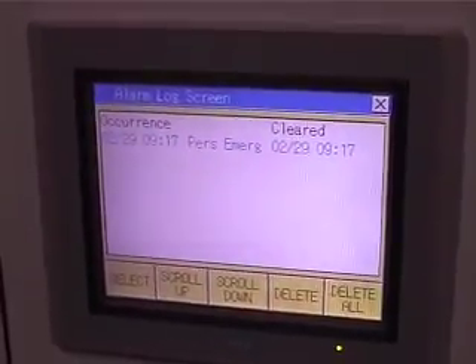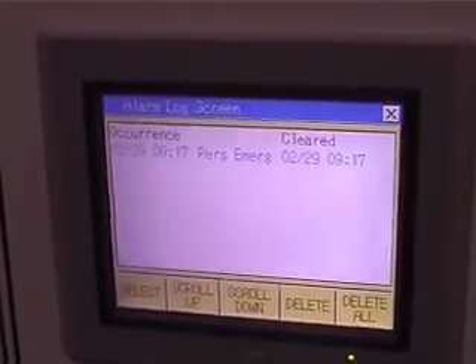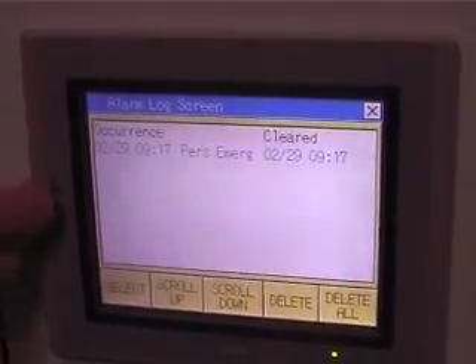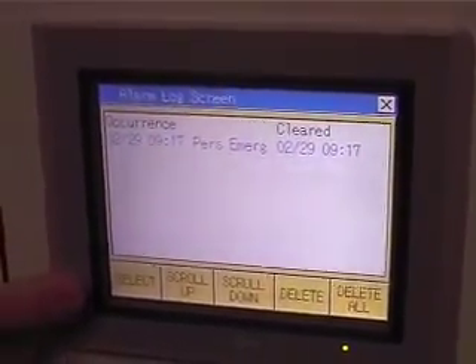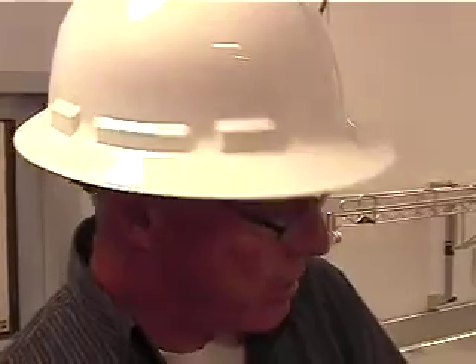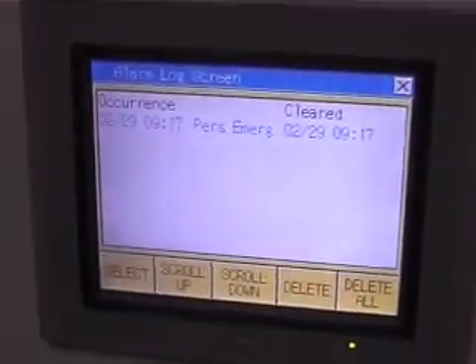Alarm log. We'll go ahead and cover this one because I usually wait till last and I'm out of gas by then. This is the log that's going to keep all the things that happen in this, including if somebody turns the fan switch off, it'll tell you that's happened. All the alarm situations, and the personal emergency alarm. If somebody hit, like we just did a few minutes ago, we hit the personal emergency alarm, it actually will log that. It'll tell you that you had an issue. If it's in blue, that means it's cleared.